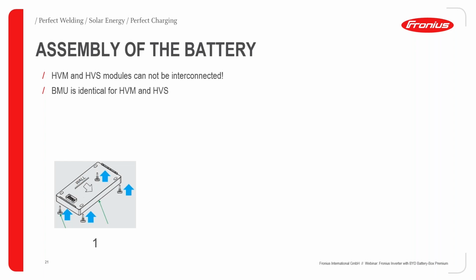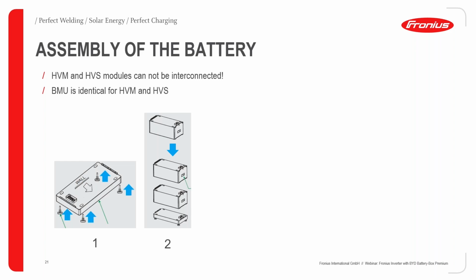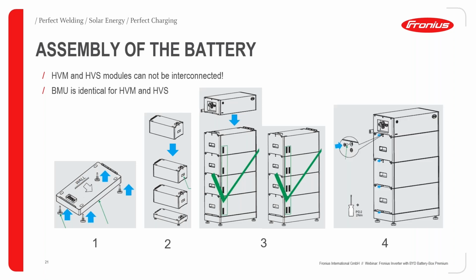The HVM and HVS modules can't be interconnected, and the BMU for the HVM and HVS is the same, but in this case we're just using the HVM. You start with your base, level it out with a level, and then each module stacks on top of each other. Then you've got the locking screws which lock each device in with each other—pretty straightforward. The BMU goes on top, then you've got your mounting bracket which mounts into the BMU, and that prevents the battery from being tipped over, keeping it solid on the wall.